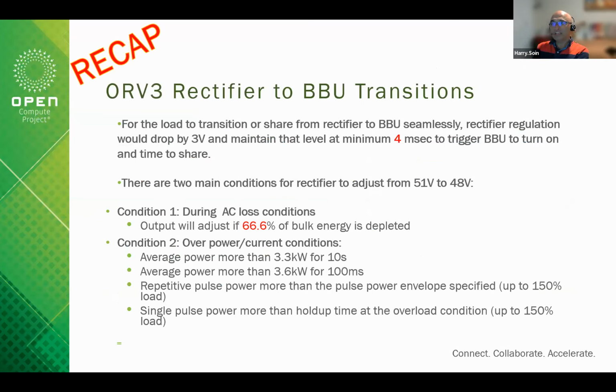Moving on, I want to recap the area where we've worked closely, especially with Meta - glad to report AE has made a significant contribution in helping to understand peak shaving: how we transition from rectifier to BBU and how the unit performs. As a recap, the BBU triggers when the rectifier voltage drops by 3 volts - that hasn't changed. What has changed is previously there was about 4 milliseconds to trigger BBU, and during that time output adjusts when 66% of the energy was depleted. The other condition was average power more than 3.3 kilowatts for 10 seconds, and 3.6 kilowatts for 100 milliseconds.